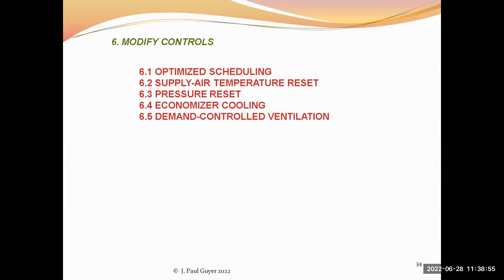And this can be a substantial improvement in energy consumption, because the more outside air you bring into the system for ventilation purposes, all of that air has to be either heated up or cooled down, whichever is required to meet the comfort needs in the occupied spaces.